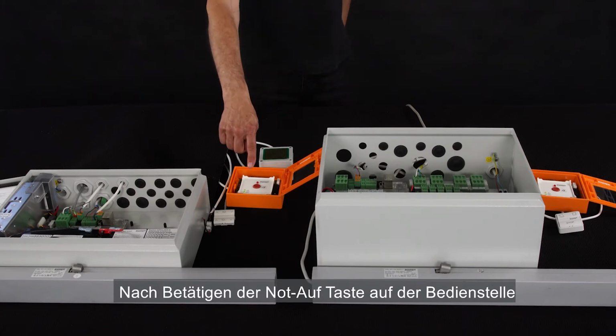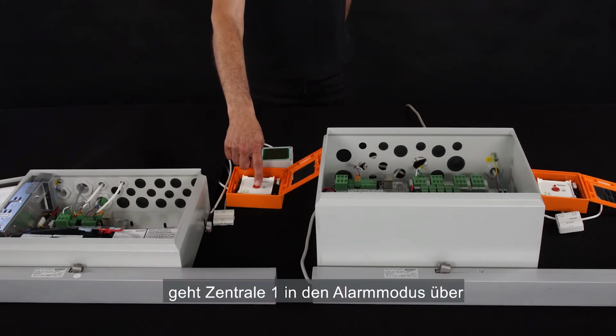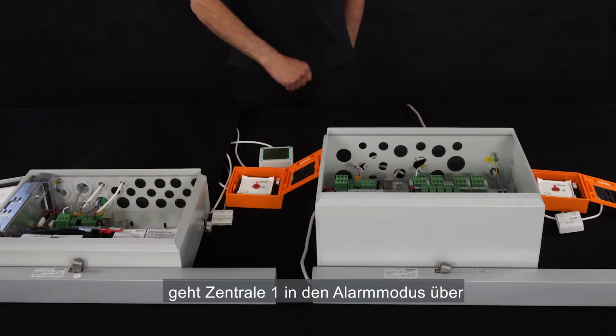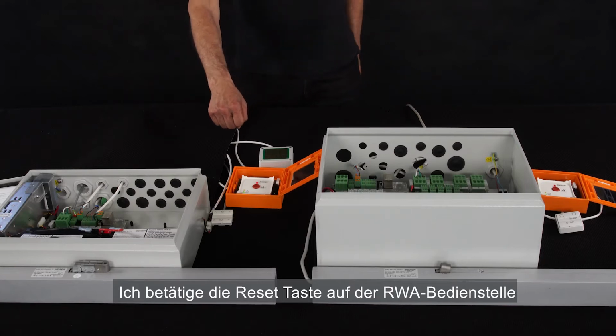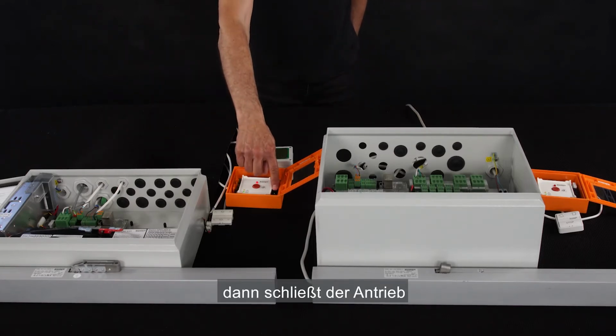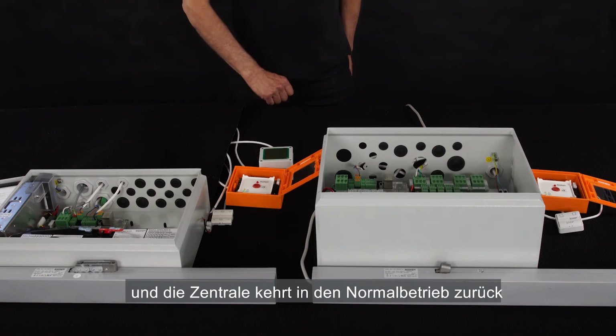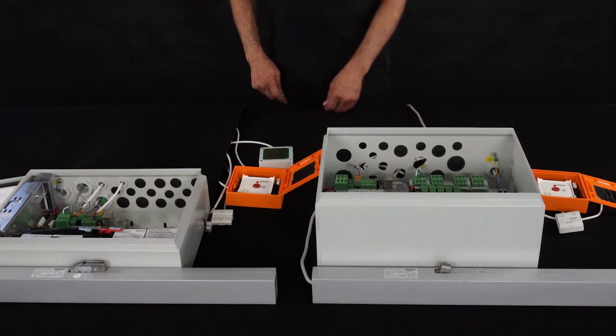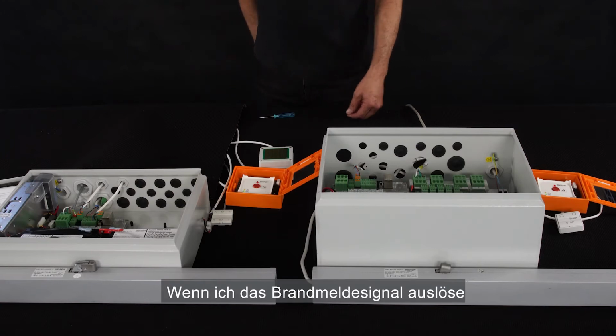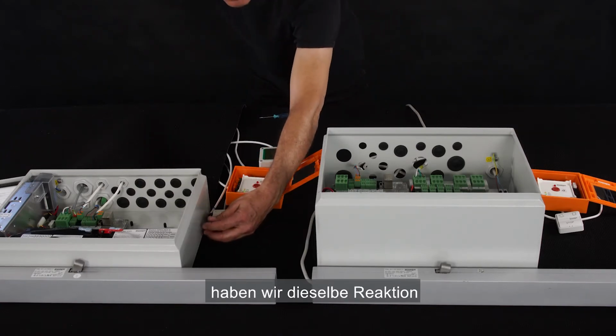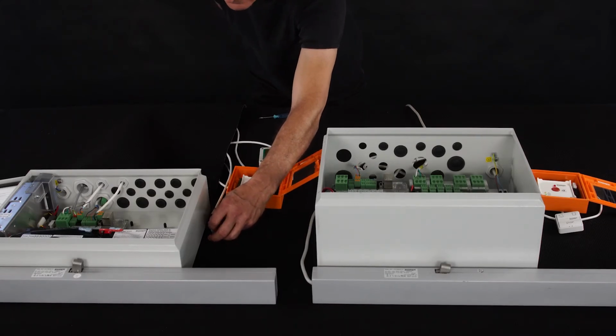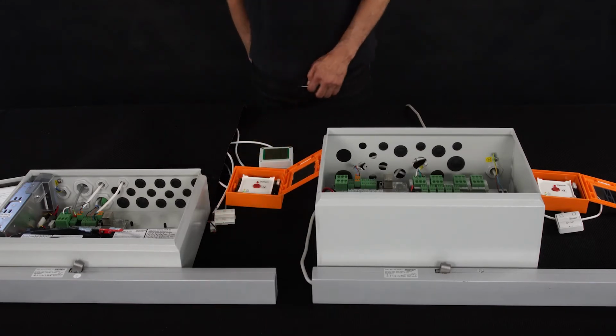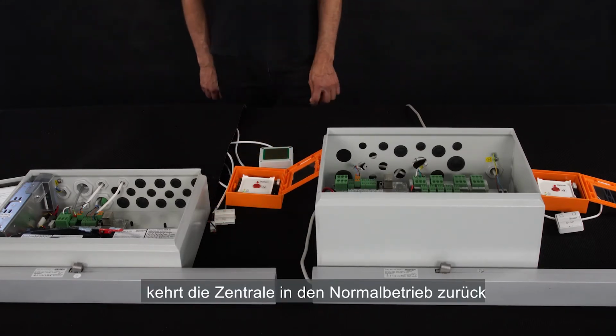If I press the red button on the break glass unit, panel 1 changes to alarm mode and the actuator opens. I press the reset button on the break glass unit and the actuator closes and the panel goes back to normal mode. If I activate the signal for the fire alarm, we have the same response. When I deactivate the signal, the panel goes back to normal mode.